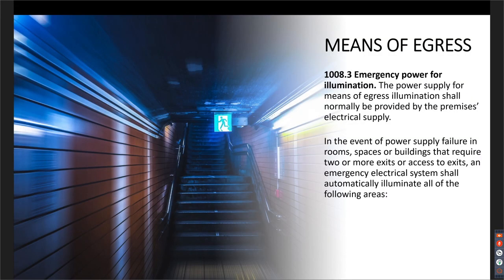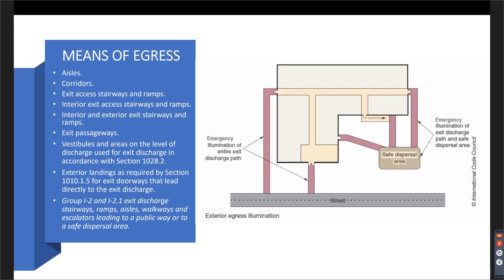Go ahead. Moving into section 1008, which deals with exit illumination. It's not a surprise that the power supply for the means of egress has to be provided from the premises electrical supply. This will be normal power. But in the event of a power failure, spaces or buildings that require 2 or more exits have to have an emergency electrical system that will automatically illuminate all of the following things: aisles, corridors, exit access stairways, ramps, interior exit access stairways and ramps, and so on.